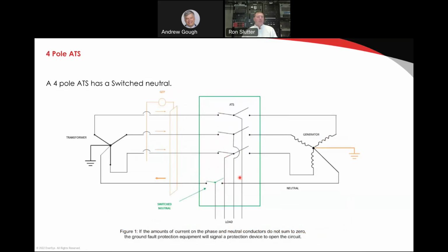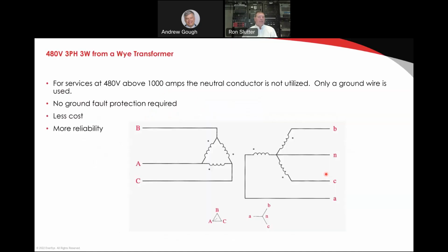And this creates some very specific changes that are required if you use 480Y277. I'm going to show you how to get around that in a few minutes, but for now, know that this creates an environment where you have to spend a lot more money because you need a 4-pole ATS rather than a 3-pole. You've got to have a ground fault protected main service. You actually have to do additional steps to the generator as well. You need to do a ground fault alarm on each circuit breaker. So there's a lot that has to happen if you get beyond a particular capacity.